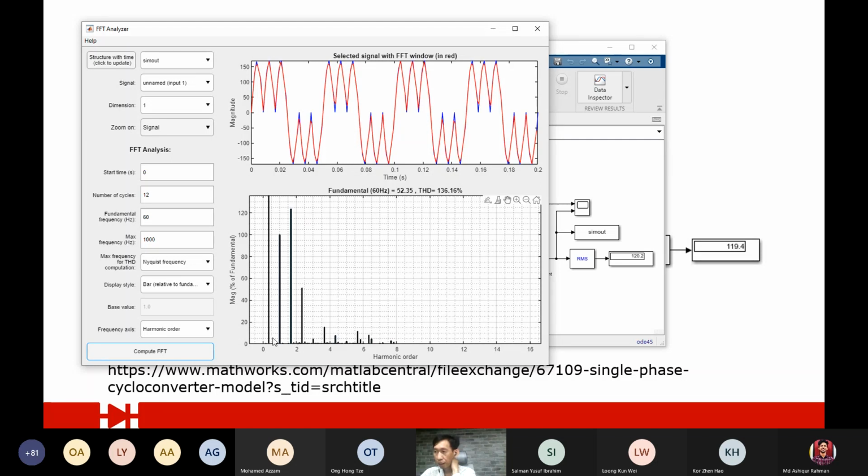So all the harmonics here are considered low order harmonics, because the operating frequency is 20 Hertz. So it's considered subharmonic, meaning that the fundamental is 60 and your harmonic is lower than the fundamental; we call it subharmonic. Subharmonic does not produce that much heat compared to the high order harmonics, the third, fifth, seventh, eighth harmonic and so forth. Even if their magnitudes are very low, like 3% or 4%, they will generate very high heat.